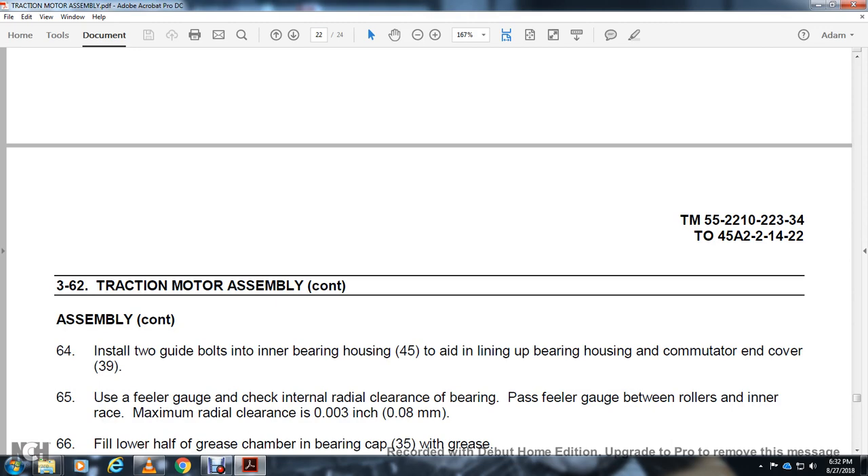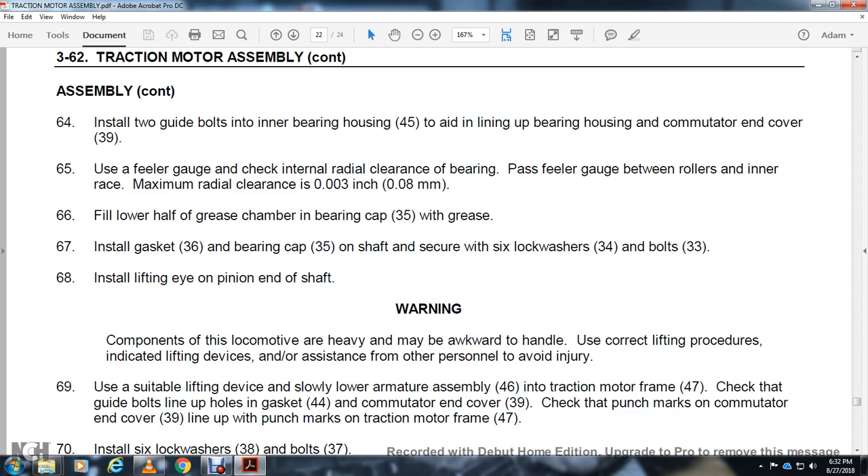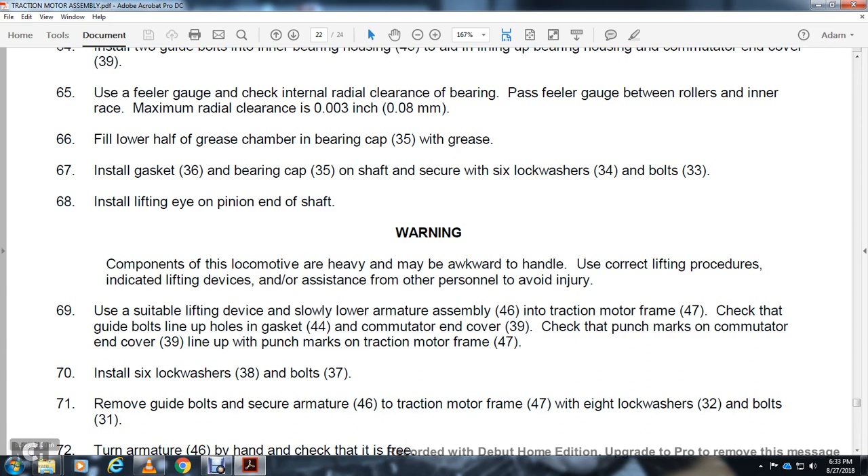Use feeler gauge to check internal radial clearance of the bearing — place feeler gauge between the rollers and inner race. Maximum radial clearance: 0.003-inch. Fill half of the lower grease chamber in bearing cap 35 with grease. Install gasket 36 and bearing cap 35. Secure with lock washers 34 and bolts 33. Install lifting eye on the pinion end of the shaft. Warning — components of the locomotive are heavy and may be awkward to handle. Use correct lifting procedures with lifting devices and other personnel to avoid injury. Use suitable lifting device to lower armature assembly 46 into traction motor frame 47. Check guide bolts align with holes in gasket 44 and commutator end cover 39. Check punch marks on cover 39 align with punch marks on traction motor frame 47. Install 6 lock washers 38 and bolts 37. Remove guide bolts and secure armature 46 to traction motor frame 47 with 8 lock washers 32 and bolts 31. Turn armature 46 by hand and check that it spins freely.